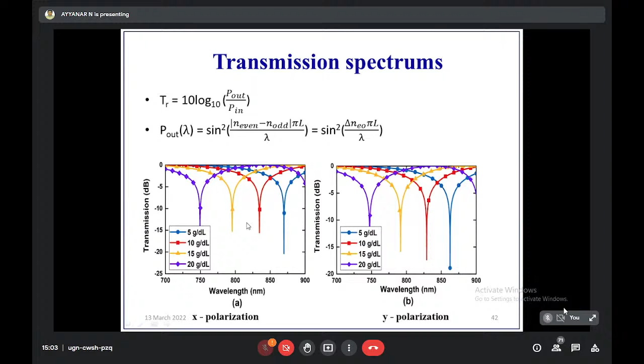Here we display the peak wavelength with respect to hemoglobin concentration from 5 gram per deciliter to 20 gram per deciliter. From this graph, we obtain high linearity. Based on the least mean square method, we can calculate the linear fitting equations. For X polarization, minus 7.992 times hemoglobin concentration plus 912.25. For Y polarization, minus 7.66 times hemoglobin concentration plus 903.35.